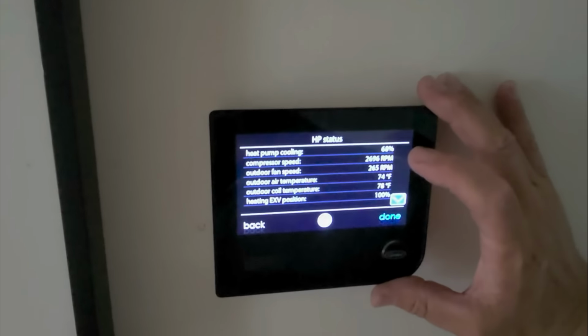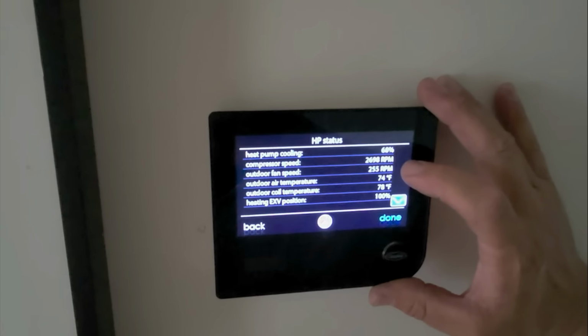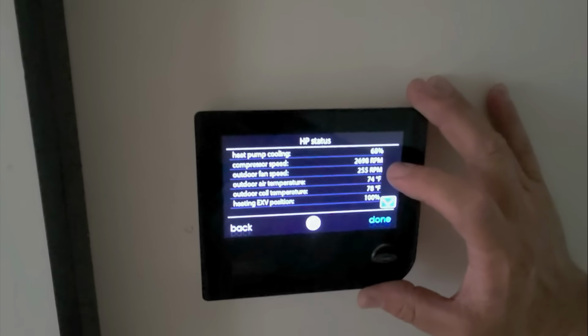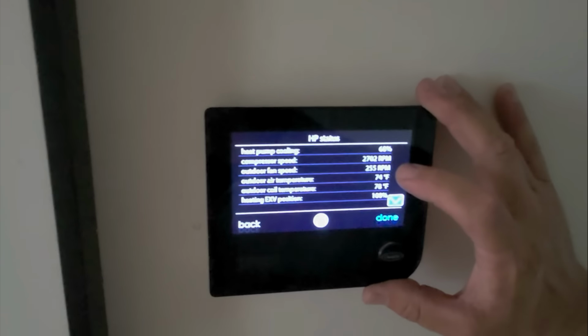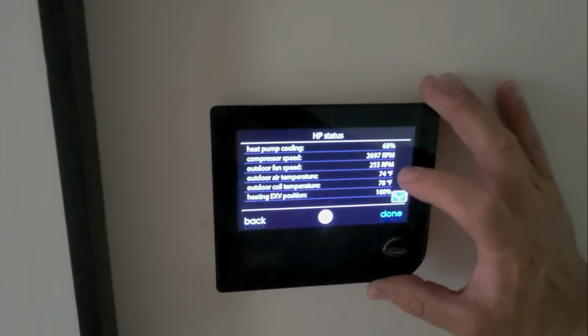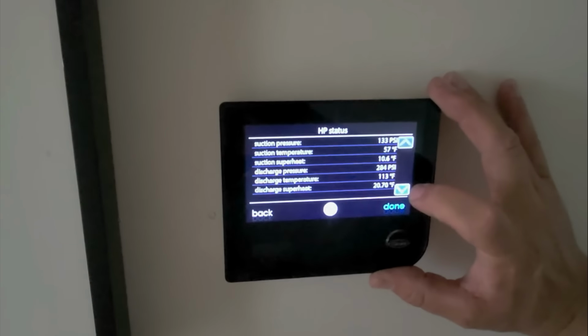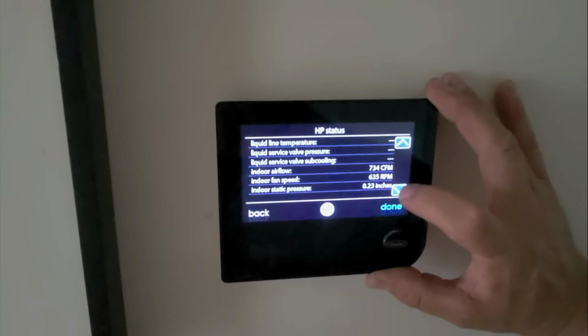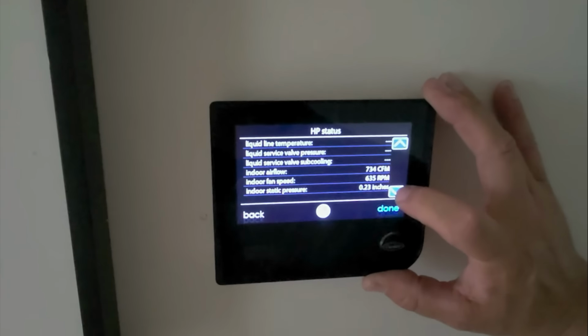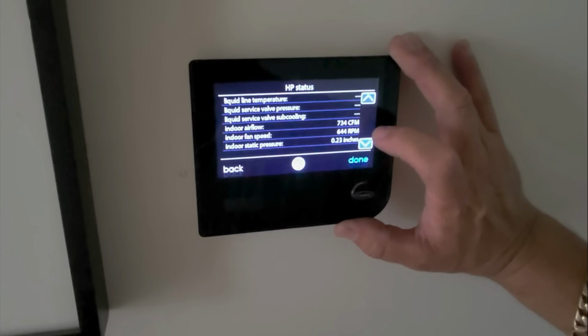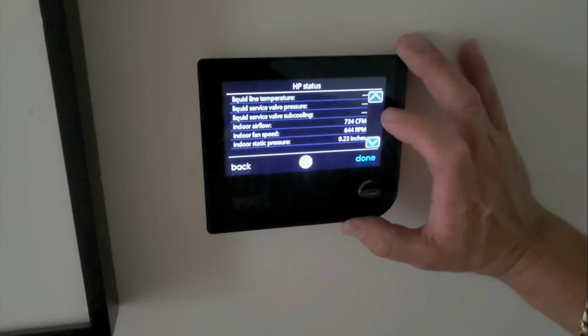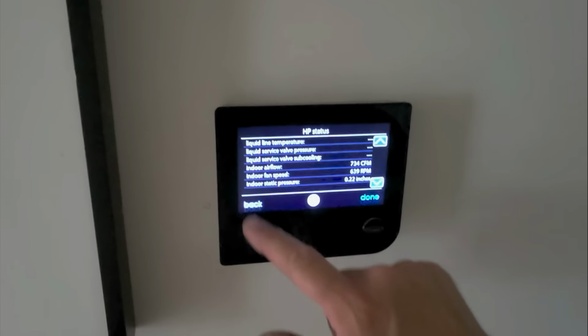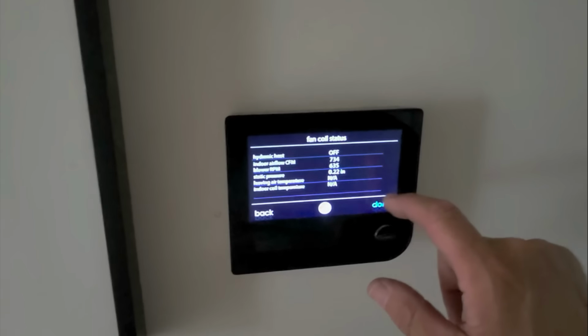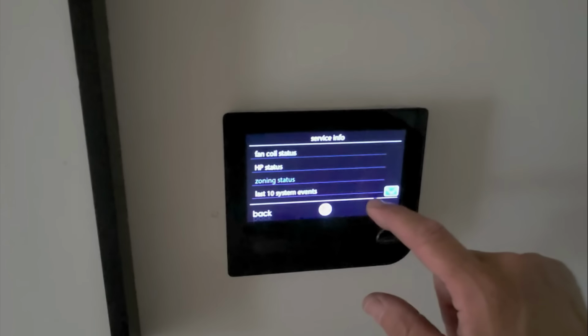All right, current status 68%. That inverter driven compressor running at a little under 2,700 RPMs. Outdoor fan speed 255. Indoor static pressure is 0.23. 734 CFM. Fan coil status. Okay.